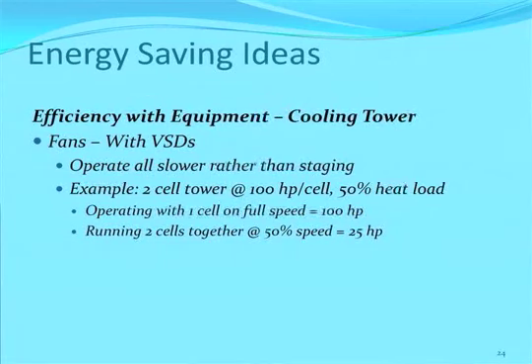Once again, with the VSDs on your fans, one idea that's particularly useful in your cooling tower, if you have multiple cells, is to run all of the fans at the same time rather than staging them. Here's an example of a 2-cell tower. If there's a 100 horsepower fan in each one of them, but you're only at 50% heat load or cooling load, then if you ran one fan, it'd run 100 horsepower at full speed. If you ran both cells, but you could run them both at half speed, you'd be down at a quarter of that horsepower. Again, that's the old power law.